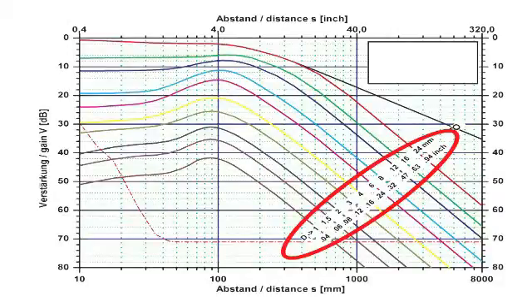As described, the determination of the equivalent reflector size is based on the comparison of two echo amplitudes. The echo from an unknown reflector is compared with the echo from a known one or a reference reflector. In practice, different types of reflectors can be used as reference reflectors.